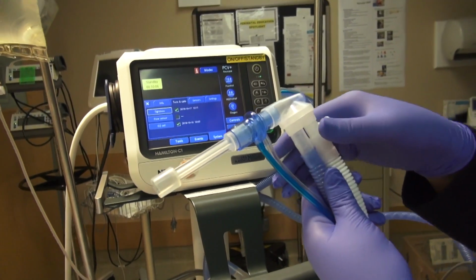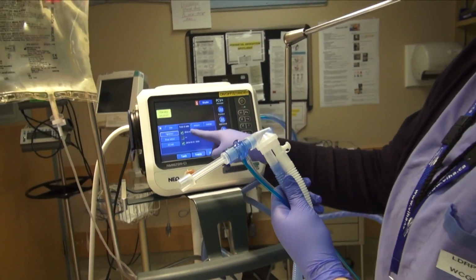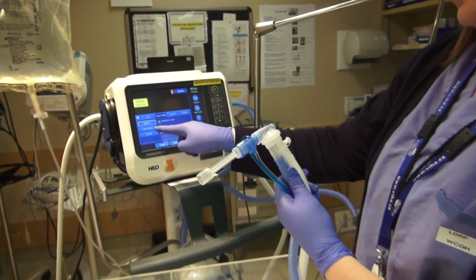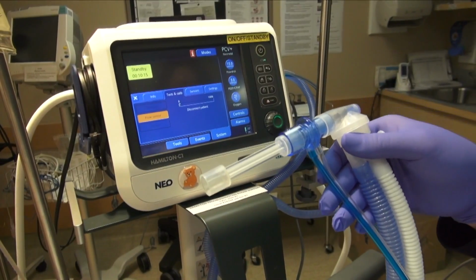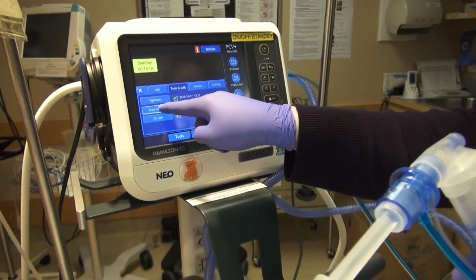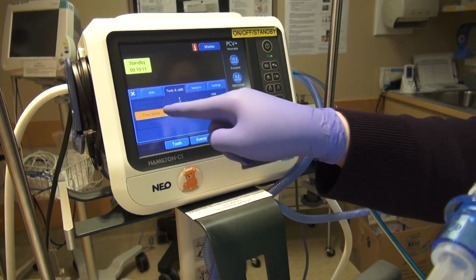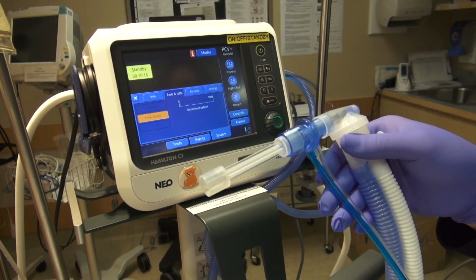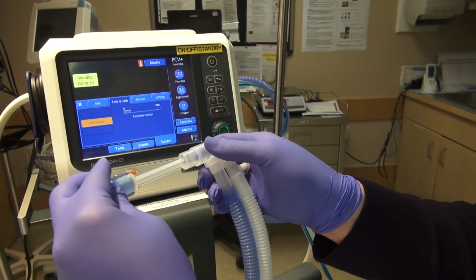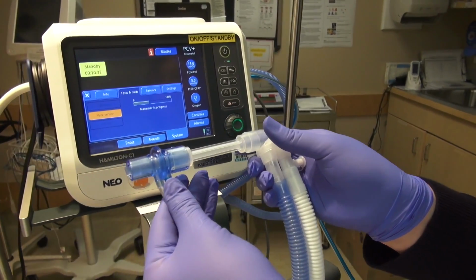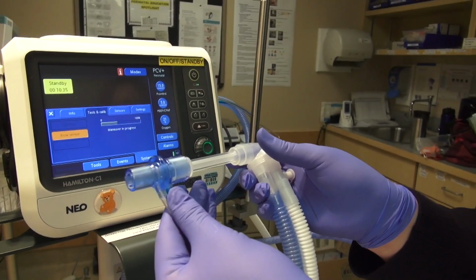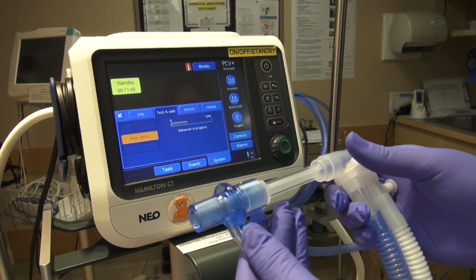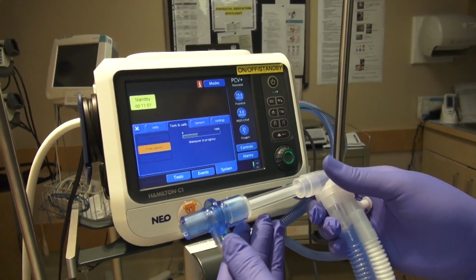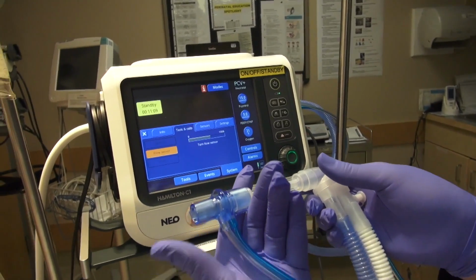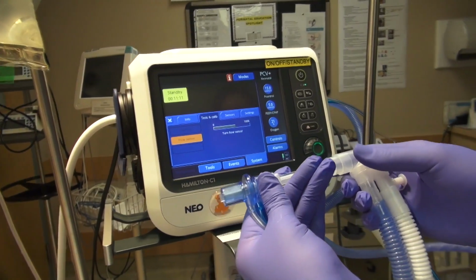Flow sensor check. For this step, the vent will prompt you to turn flow sensor. You will need the calibration adapter still attached for this step. Hit flow sensor button. When prompted, turn flow sensor around as indicated and attach the calibration end to the Y piece. When prompted to turn the flow sensor again, remove the calibration adapter and turn the flow sensor back to its starting position.